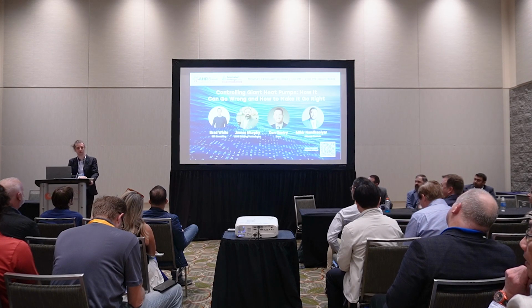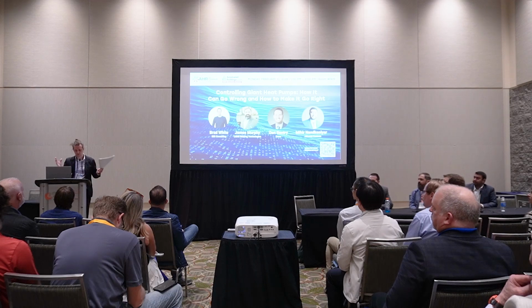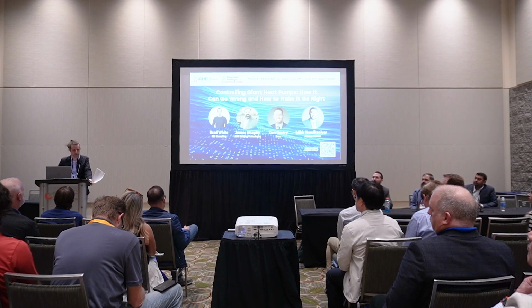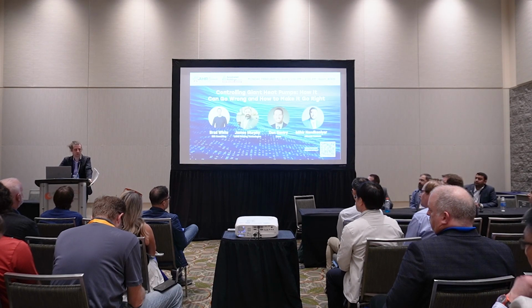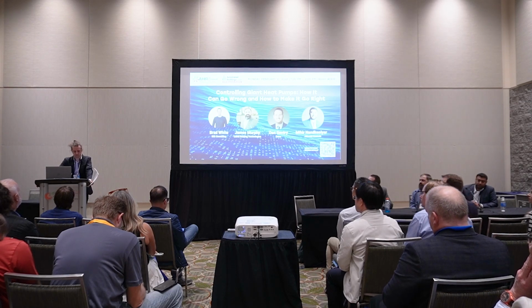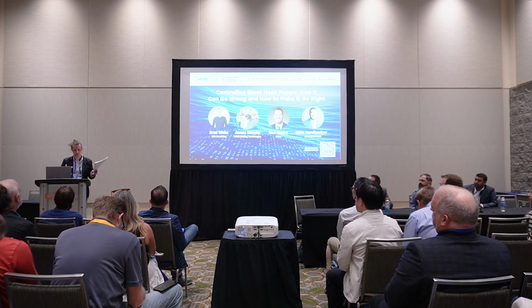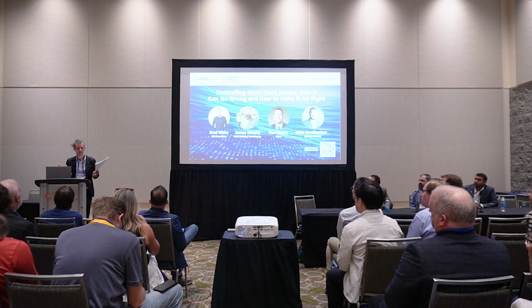Another project that we actually designed ourselves: a brand new central heat pump for an office building, I think a 200,000 square foot office building. It's a 200-ton heat pump. Lots of conversations with the distributor. We designed around a particular product. Great, it's all designed. We need 130, 135 degree water. Yeah, no problem. Unit's rated for that. Fantastic. Unit comes to site.